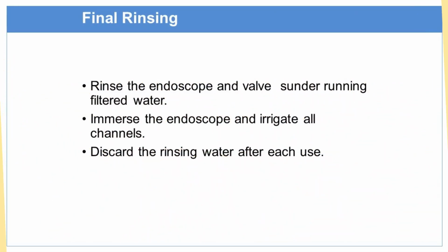If that machine or any automated machine stops due to electric interruption or any other reason, the cycle should be restarted. You must repeat that process to give proper time for its disinfection. Final rinsing: rinse the endoscope and valve under running filtered water. Immerse the endoscope and irrigate all channels very carefully. Discard the rinsing water after each use.